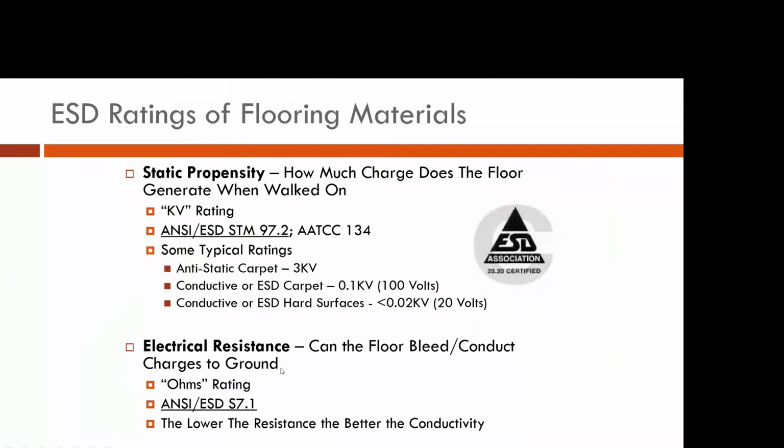These are all measured in ohms, which is a measurement of resistance, and you would use what is called a megohmmeter. There are various meters out there. Some are analog. You set your meter to the appropriate voltage, and then you push a button, very simple, quick, and easy, and it runs all the way up through testers that have digital storage.